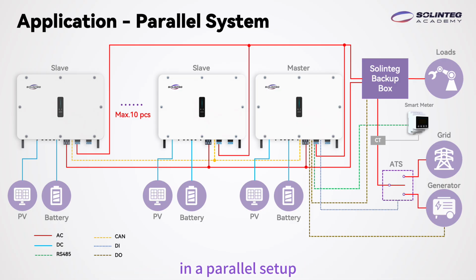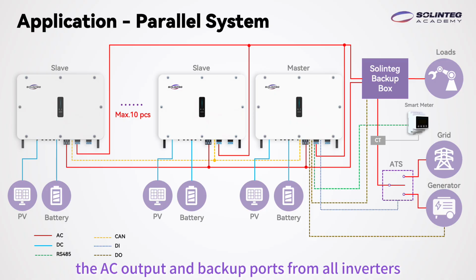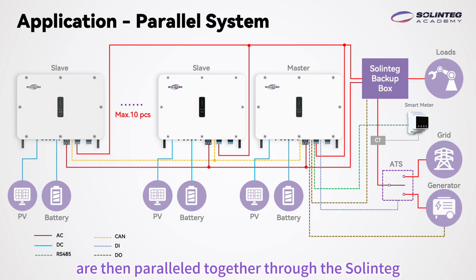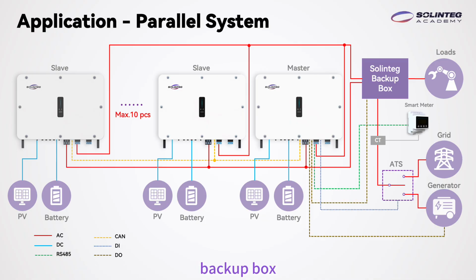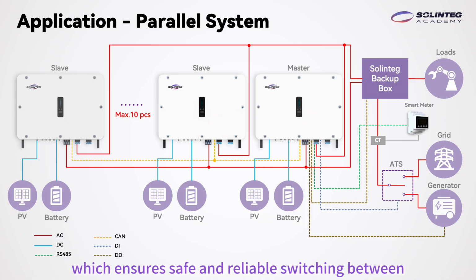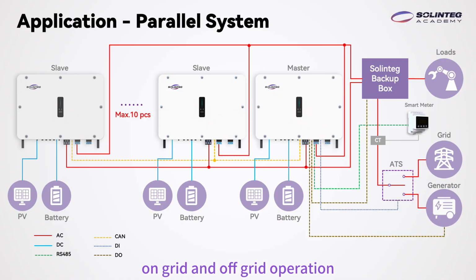In a parallel setup, each inverter independently connects to its own PV array and battery bank. The AC output and backup ports from all inverters are then paralleled together through the Solinteg backup box, which ensures safe and reliable switching between on-grid and off-grid operation across the entire system.